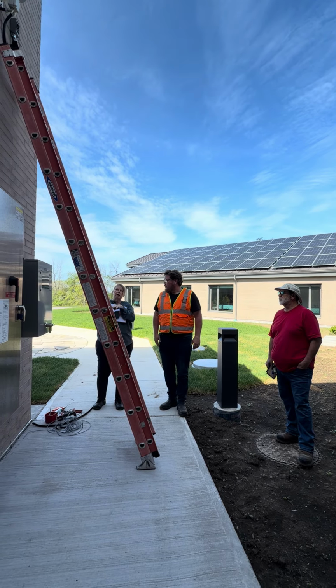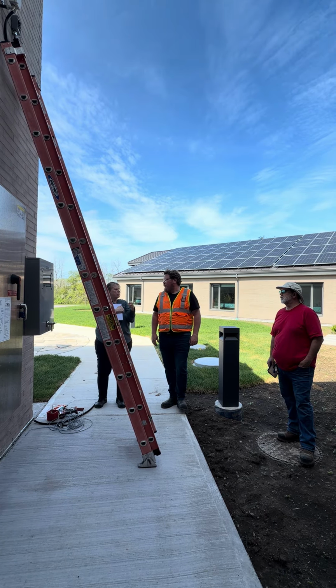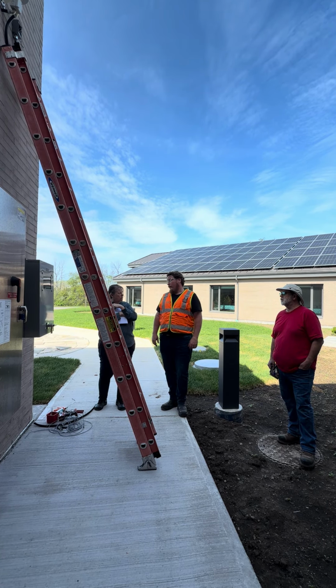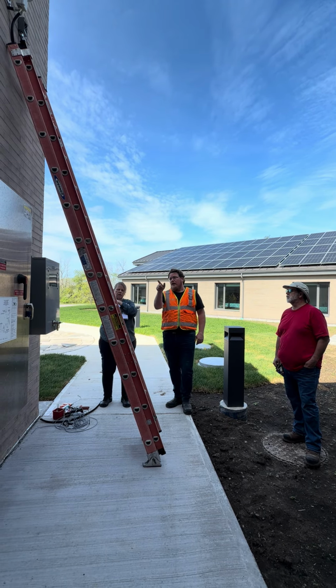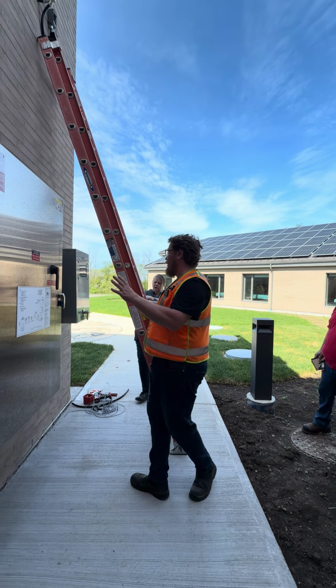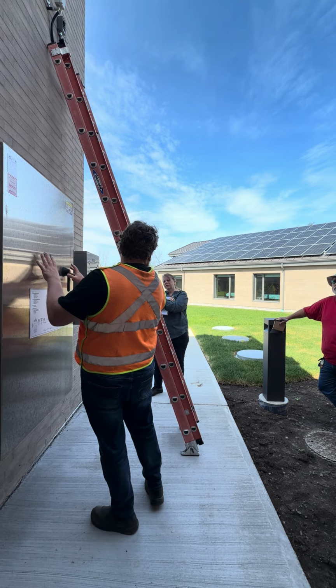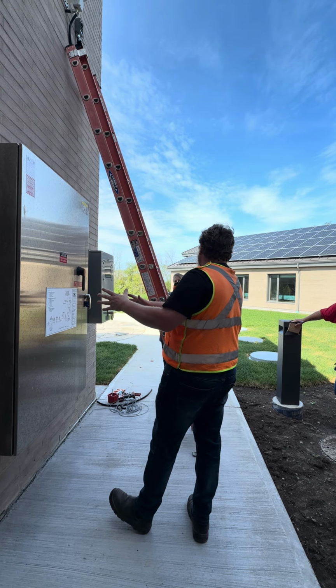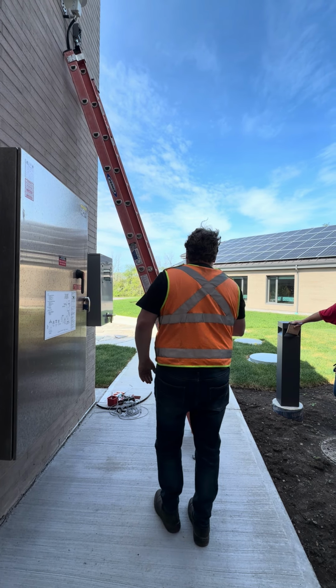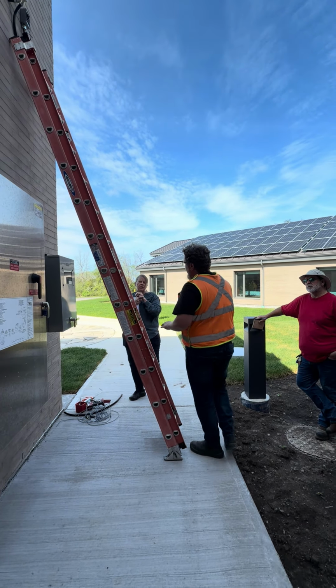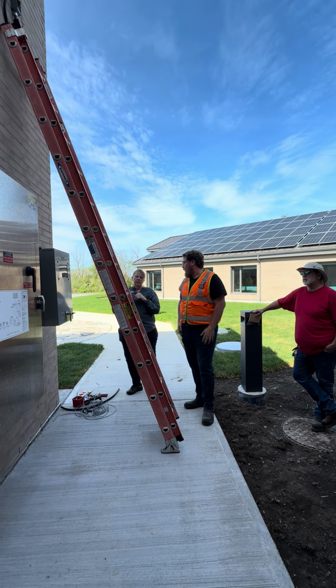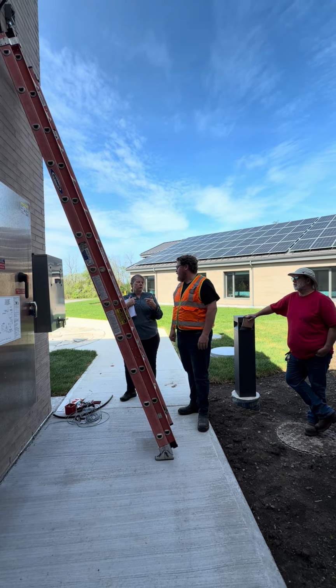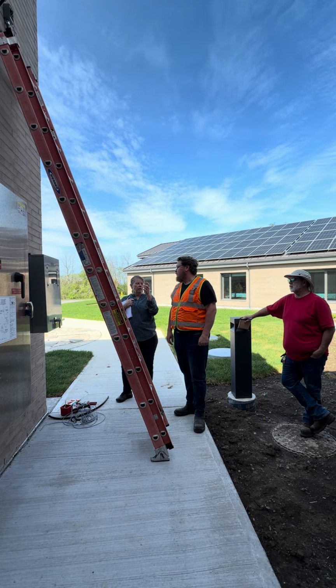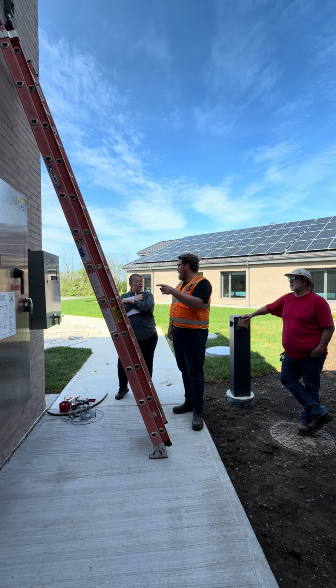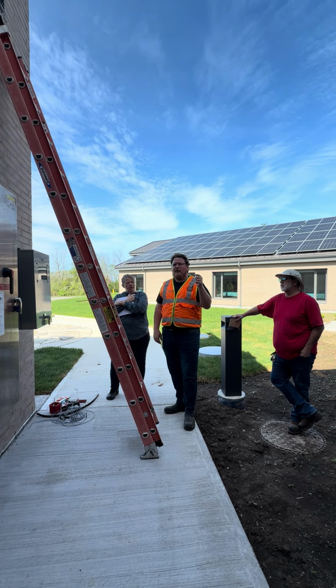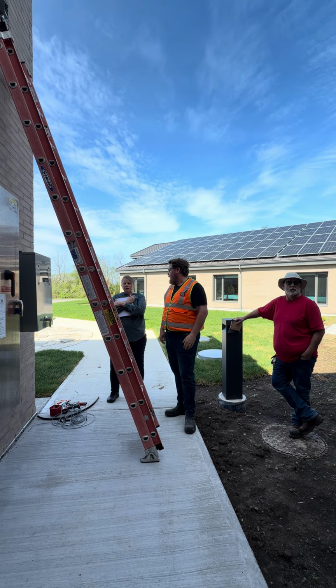So what happens internally for us, for our building, if you shut it off at the street, but we're still generating energy from the power? You won't. That's a really important, good question. The way that disconnect works, this actually still hasn't connected into your building yet, and this is where they're basically isolating. There's what's called a contactor in there, and that trip will isolate the contactor. So it doesn't interrupt the building power, but it would interrupt the solar. So it automatically turns the solar off. I'm not getting an increased energy bill from solar that's stockpiling somewhere, right? No. If they turned it off and left it off for a couple weeks, you would see an increase in your electricity bill because it's not offsetting the energy. Does that make sense?